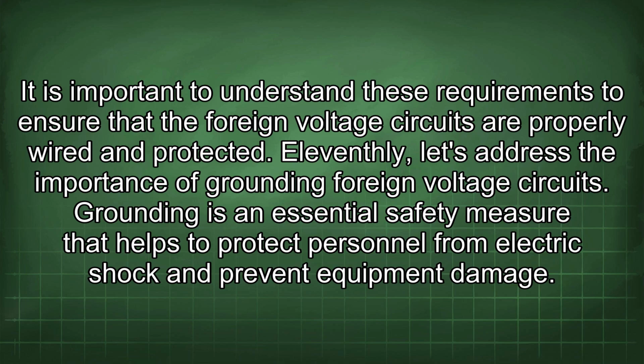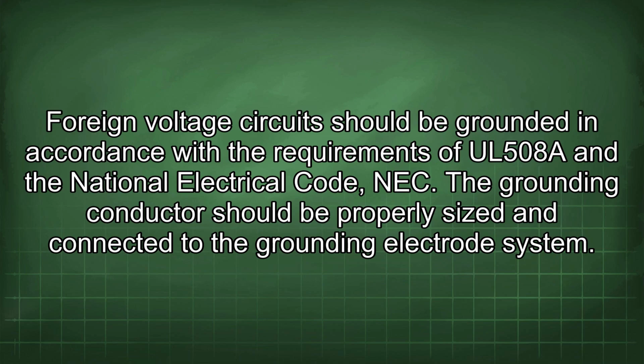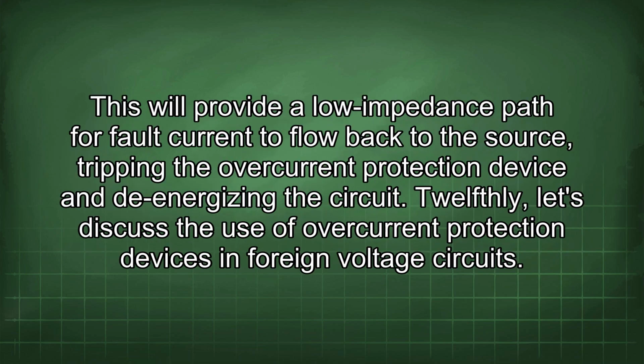11thly, let's address the importance of grounding foreign voltage circuits. Grounding is an essential safety measure that helps to protect personnel from electric shock and prevent equipment damage. Foreign voltage circuits should be grounded in accordance with the requirements of UL508A and the National Electrical Code (NEC). The grounding conductor should be properly sized and connected to the grounding electrode system. This will provide a low impedance path for fault current to flow back to the source, tripping the overcurrent protection device and de-energizing the circuit.